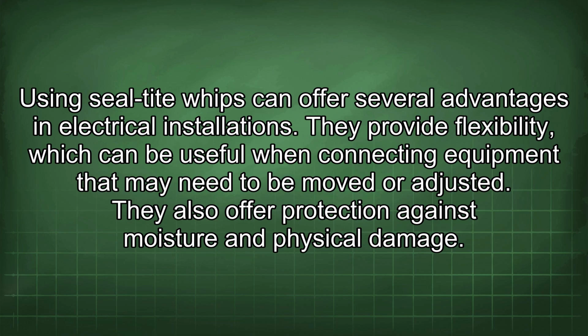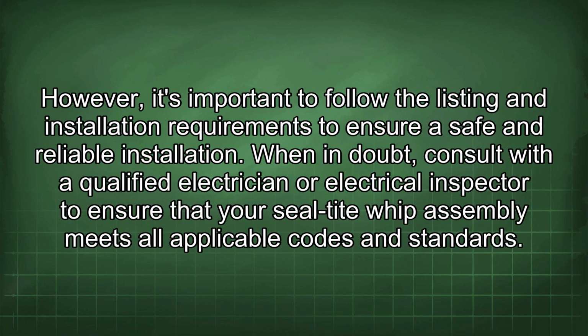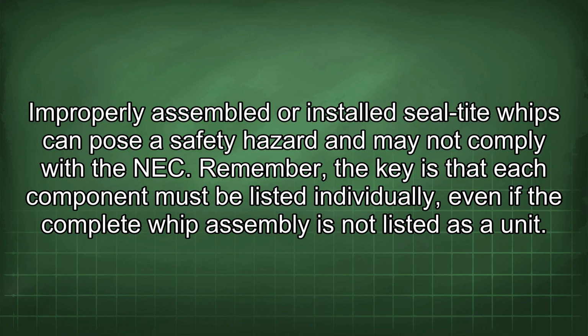They also offer protection against moisture and physical damage. However, it's important to follow the listing and installation requirements to ensure a safe and reliable installation. When in doubt, consult with a qualified electrician or electrical inspector to ensure that your Seal-Tite whip assembly meets all applicable codes and standards. Improperly assembled or installed Seal-Tite whips can pose a safety hazard and may not comply with the NEC. Remember, the key is that each component must be listed individually, even if the complete whip assembly is not listed as a unit.